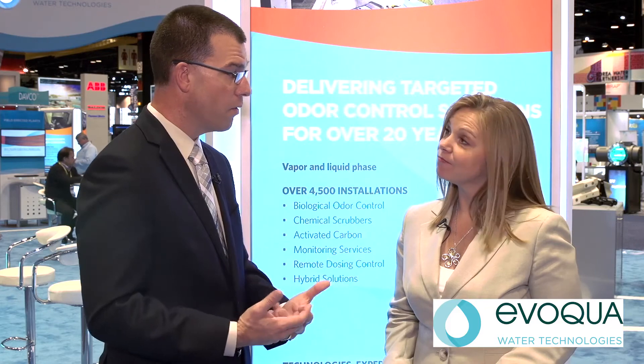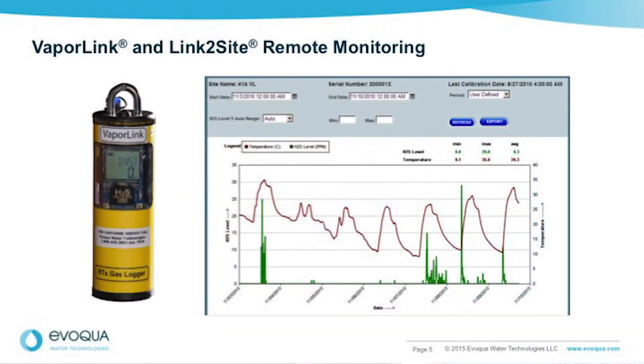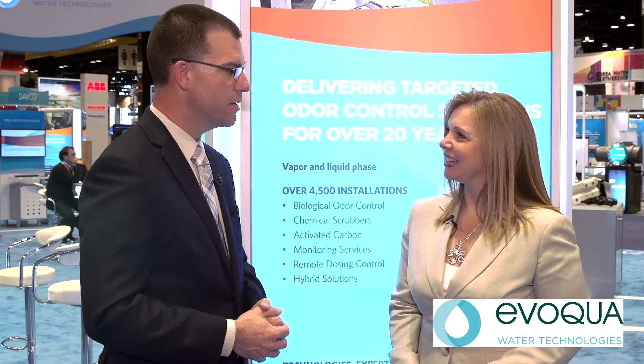Odor and corrosion are continuous problems. How do you keep it from coming back? That's the key — you don't want to just solve it once. You want to keep it solved so that your phone doesn't ring or your street doesn't collapse. Using a full-service program from Evoqua helps you do that, because we can continually operate and maintain the systems, keeping them fully functional but also very cost-efficient. We do the optimization so that in the case of a chemical, you're not overfeeding it — you're feeding the right amount. We call that dose-to-demand. We dose the amount of chemical to the demand in the system. Then we follow that up with continuous monitoring using our Link2Site system and our Vaporlink hydrogen sulfide monitors deployed at the various control points, making sure you're constantly monitoring your system.